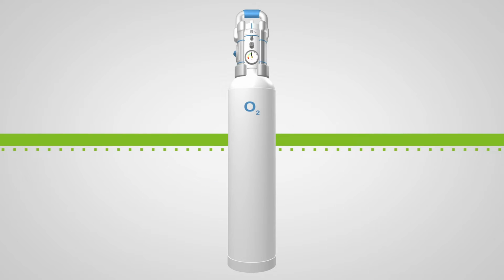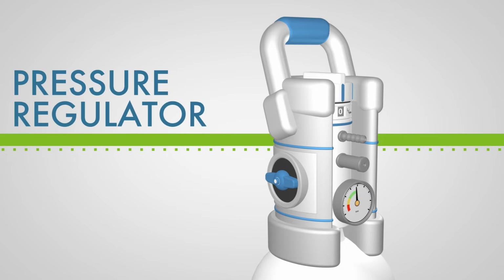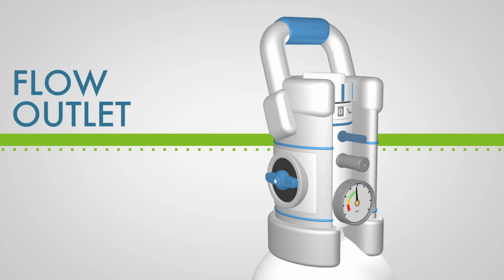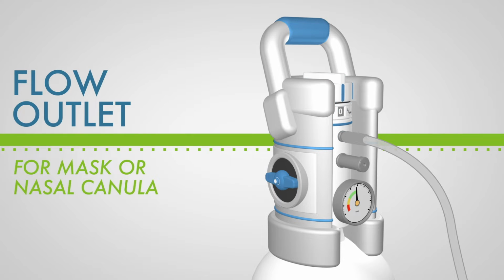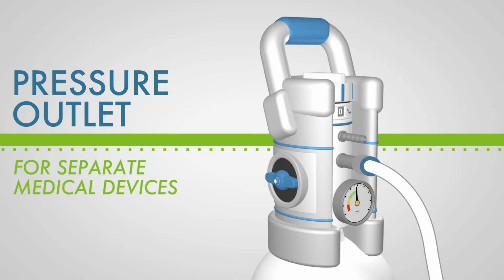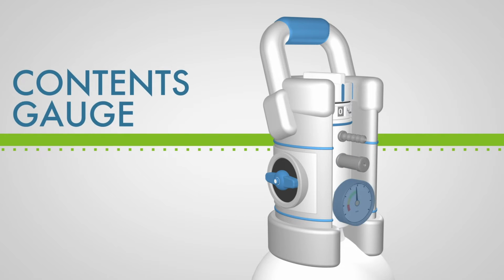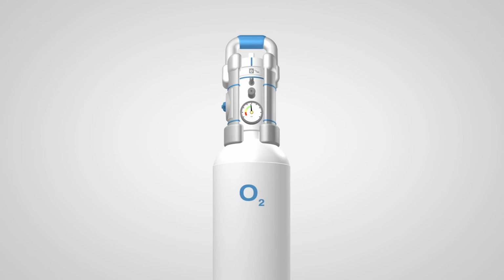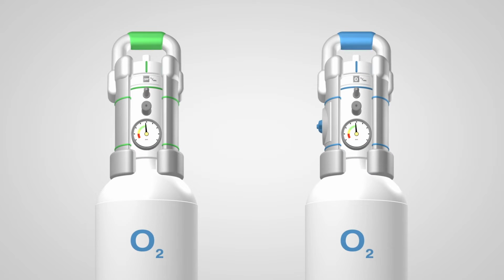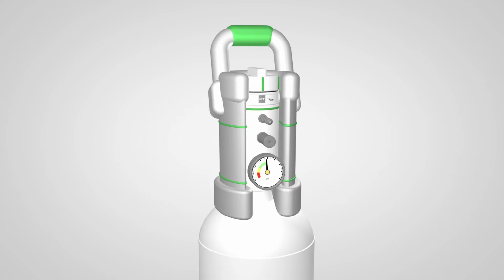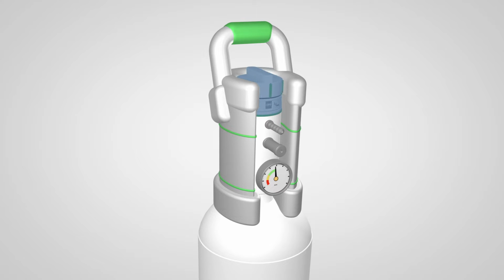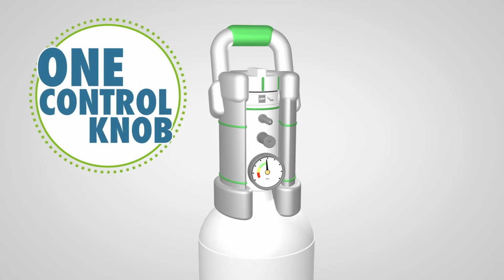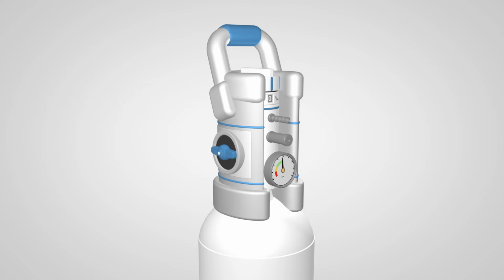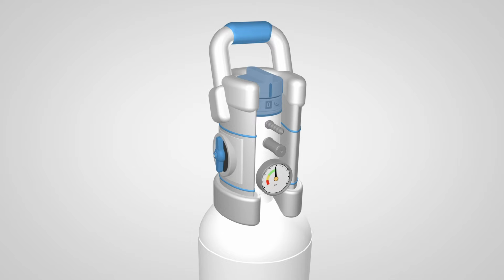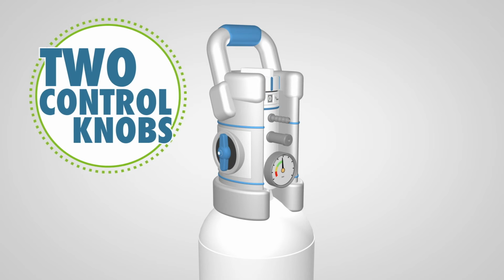We remind you that valves incorporating a pressure regulator normally have a flow selector and flow outlet for connecting to a mask or nasal cannula, a pressure outlet for connecting to a separate medical device, a contents gauge, and a valve guard. Please note that there are two types of valve that are operated differently. Some have an integrated shut-off valve and flow selector, which we will call a one-control knob valve. The other type has two separate controls, one to open the valve and the other to control the flow, which we will call two control knobs valves.